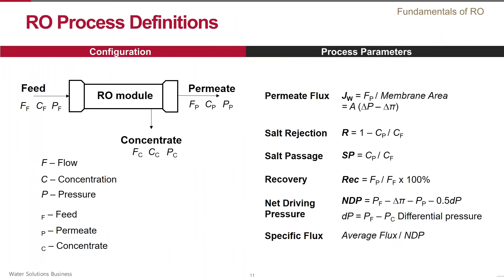In the most simplistic way, the RO process can be described by three flows: one incoming feed flow and two outgoing flows — permeate and concentrate. Each flow is characterized by its rate, pressure, and concentration of dissolved solids. The two major parameters that characterize the RO process are permeate flux — the ratio of the permeate rate to the membrane surface area Jw — and salt rejection, which is a relative measure of how much of the salt initially in the source water is rejected by the RO membrane. A closely related parameter is salt passage SP, which is simply one minus rejection — it indicates the amount of salts that remain in the permeate.